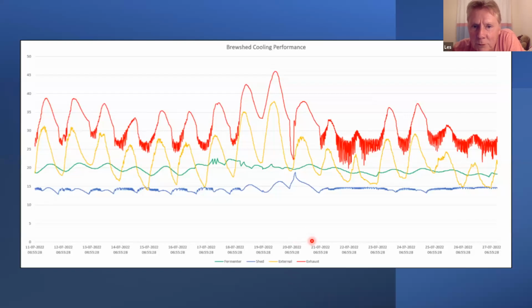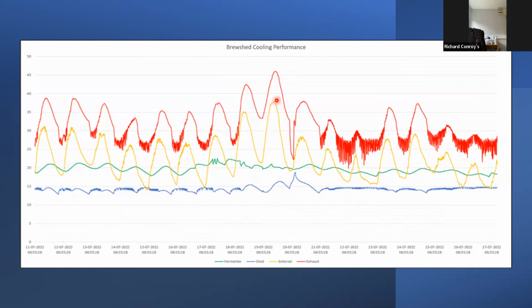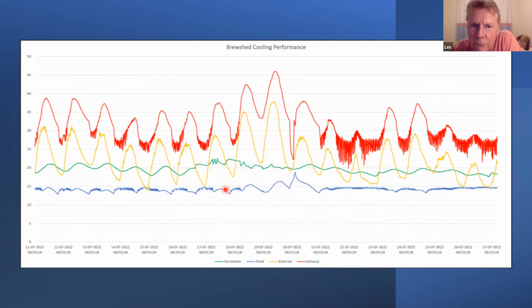That's the brewing shed temperature control performance. I won't go into detail, but the brew shed is reasonably consistent at about 13-14 degrees. The yellow line is the outside temperature - this was when we were at 36-37 degrees, getting close to 38, and the brew shed was at 16 when it should normally be 14. It was starting to lose control around 30 degrees outside, slipping a bit, going from 14 to 15 to 16.2.